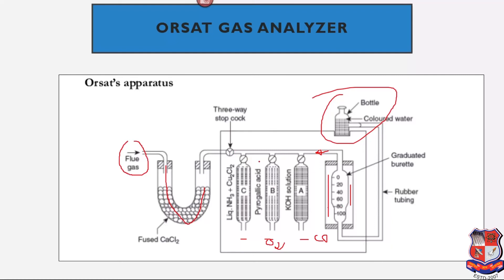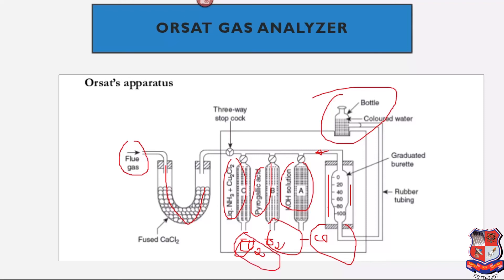Similarly, the third valve is operated: the water level in the burette rises, and the gas flows into the ammoniacal cuprous chloride solution, which absorbs CO. Since the initial mass in each chamber is already known, from the change in volume we can determine how much CO, O2, and CO2 are present in the flue gas sample. The remaining volume corresponds to N2.